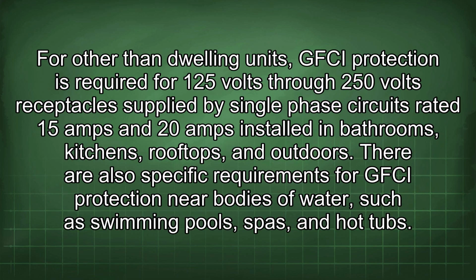For other than dwelling units, GFCI protection is required for 125 volts through 250 volts receptacles supplied by single-phase circuits rated 15 amps and 20 amps installed in bathrooms, kitchens, rooftops, and outdoors. There are also specific requirements for GFCI protection near bodies of water, such as swimming pools, spas, and hot tubs.